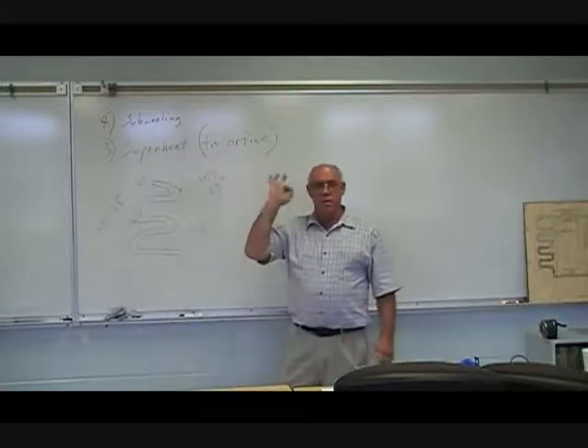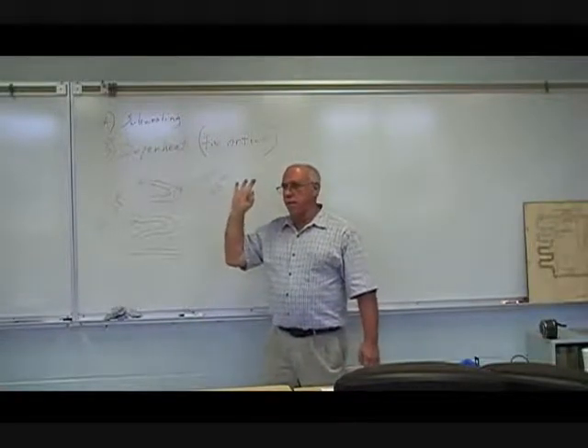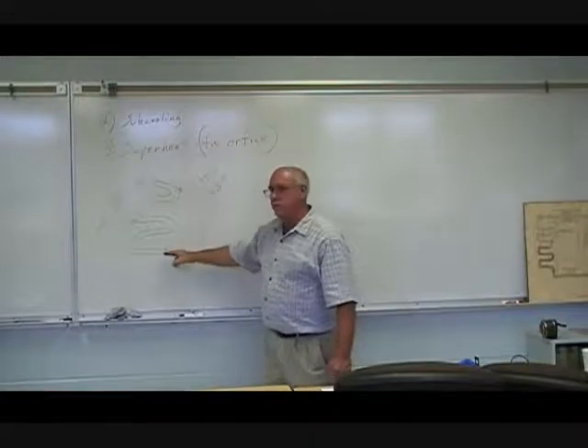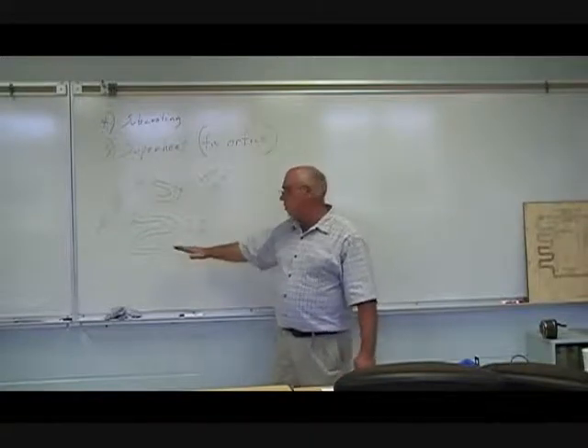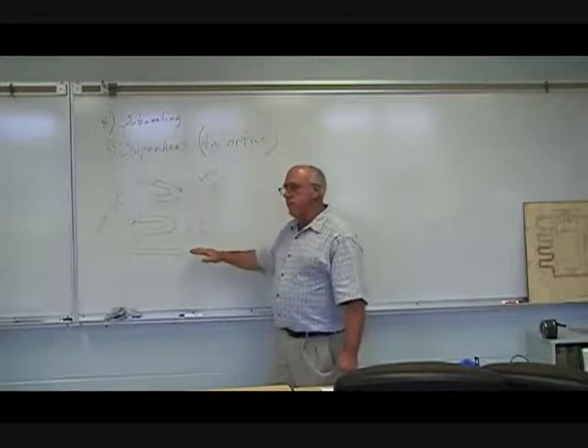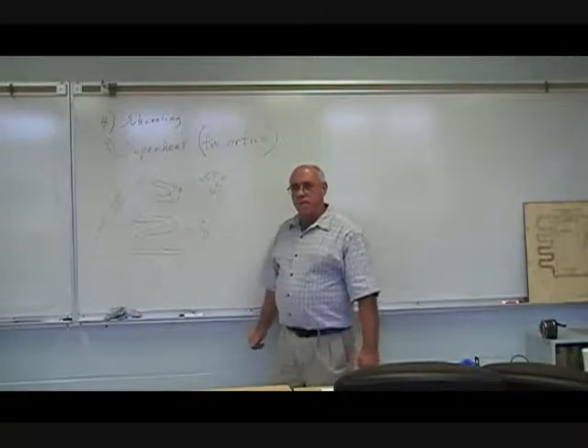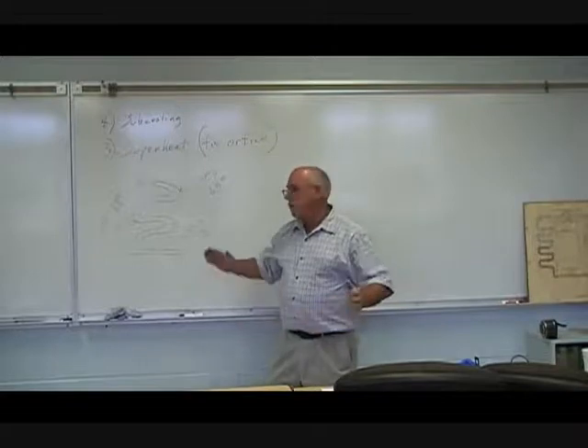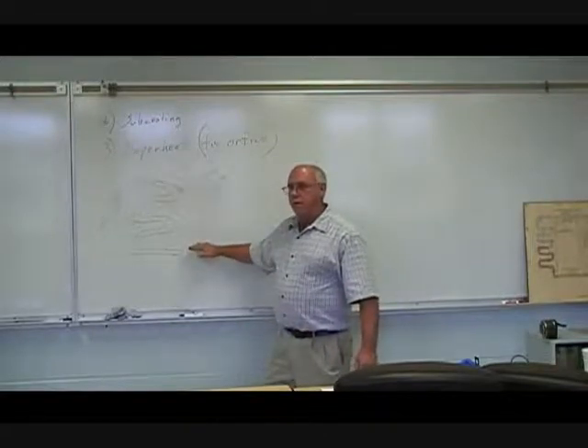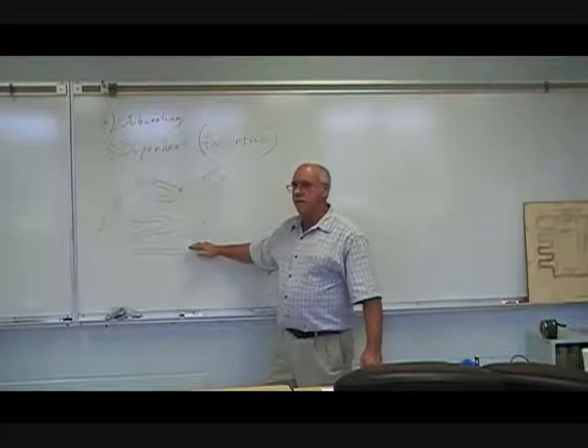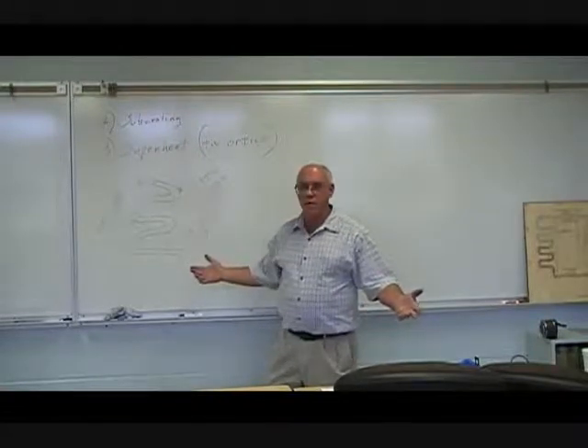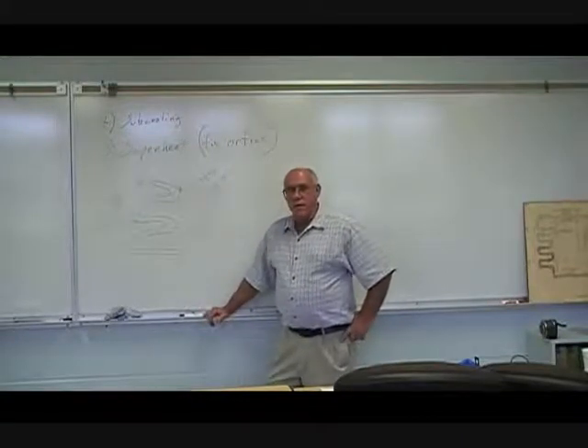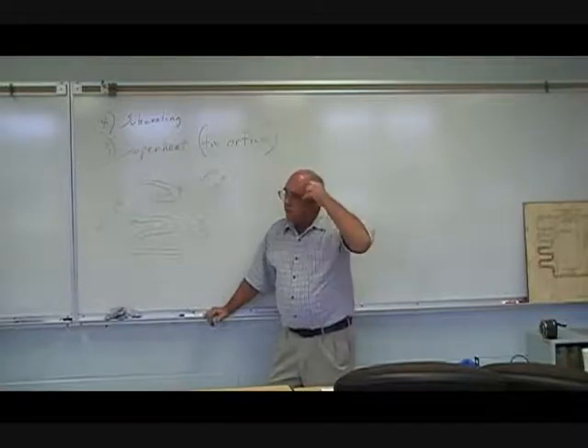Ideally, we would have this much superheat. Unfortunately, our devices today aren't that good that we can ensure that we're not going to get liquid back from the compressors, so we put a little insurance in there to make sure that we don't send liquid back. You know, I see the times coming with some of the electronic devices and all that we'll be able to reduce this superheat to where it's closer to zero. I don't think it will ever be zero because there will be no insurance at all that there will be no liquid. Of course, there are other devices that may come into play. But for right now, we're looking at around about 15 to 20 degrees.